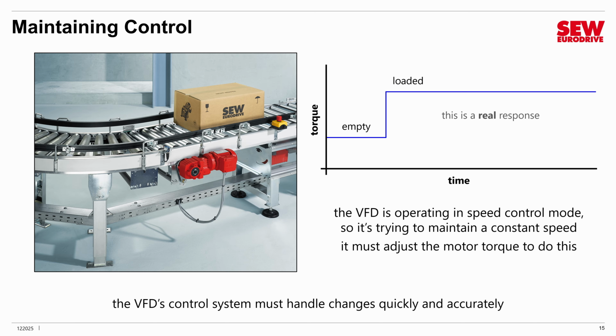What actually happens is something more like this. This is what we call a real response. There's a delay before the VFD even starts changing things, then it takes time to make that change. It probably overcompensates, and so it overshoots the required torque, and then it corrects it, undershoots it, overshoots it again, and eventually settles down to the new level. All right, the VFD is doing this every time something changes. Either you change the set point or you change the load.